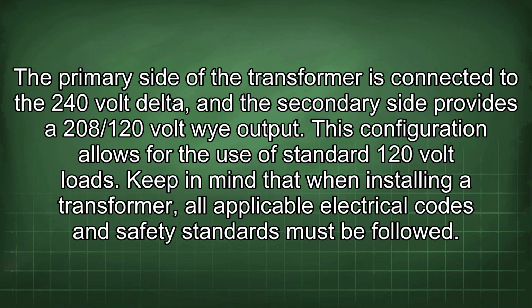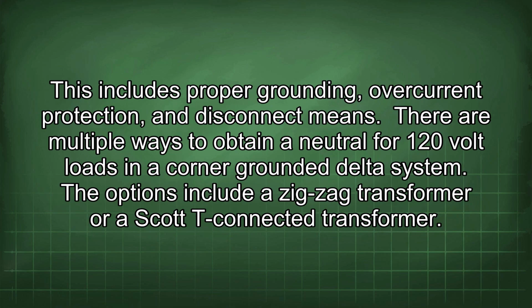The primary side of the transformer is connected to the 240 volt delta, and the secondary side provides a 208/120 volt Y output. This configuration allows for the use of standard 120 volt loads. Keep in mind that when installing a transformer, all applicable electrical codes and safety standards must be followed. This includes proper grounding, overcurrent protection, and disconnect means.